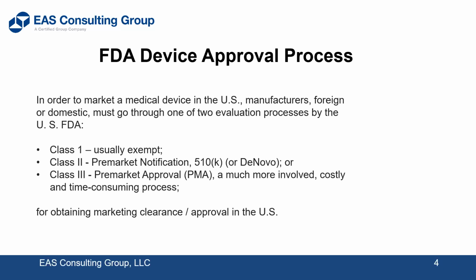So when you hear about approved products, the formal definition of approval is the PMA. If you're talking about notification, it's cleared. A 510K clears your product to market. The PMA approves your product to market. So a little definition there that we need to be aware of. I see those terms misused in marketing. Generally, the FDA does not like you to even mention that kind of thing in your marketing.